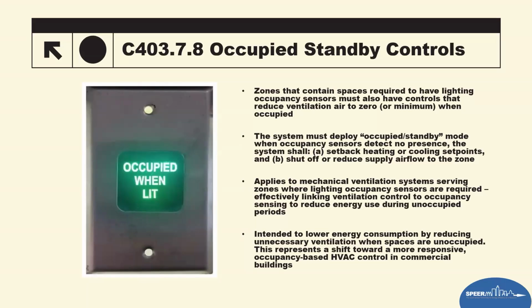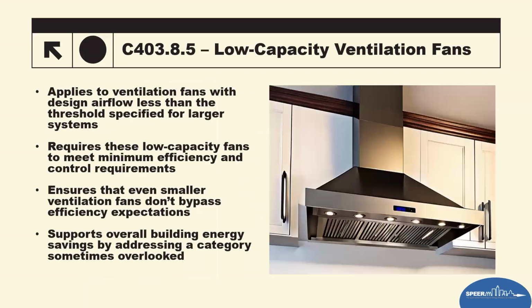So in that mode, the system reduces energy use by doing two things. First, it sets back the thermostat. And then secondly, it is either shut off or reduces air supply or supply airflow to that zone. This requirement ties in ventilation as well as HVAC operation to occupancy rather than just running continuously. So overall, this creates smarter, more responsive control strategies, keeping the occupants more comfortable when present and then saving energy when they're not.